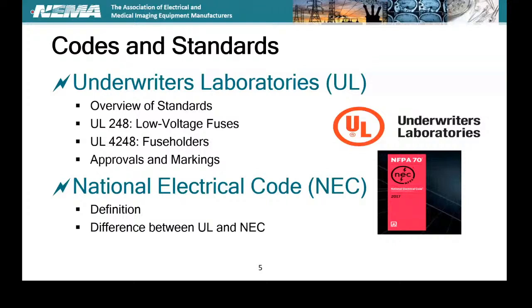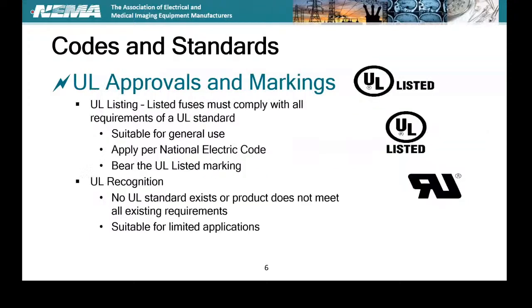Now, the bottom one is a UL recognition. You'll see there's no UL standard per se exists. Does not meet all the requirements in the standard, but it might be suitable for limited applications. So you may have, I dare say, a HVAC piece of equipment that you may have a recognized overcurrent device. It may be supplemental only, but it is now going to be only UL recognition and not UL listed. Absolutely.